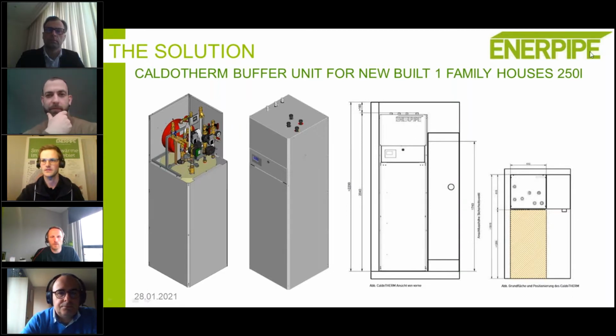Maybe to add to that, Markus, because I see the question is about heat losses moving from the distribution pipes to the tank. With the smart charging algorithm for decentralized buffers that I just explained, you move the heat into the buffers probably earlier than you would in a normal way. So you might put more heat losses into the tank than without the smart control algorithm. But on the other hand, that gives you the benefit of not having a large peak, which also impacts the heating price.